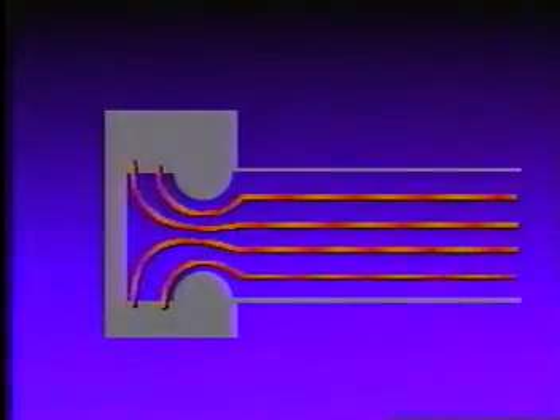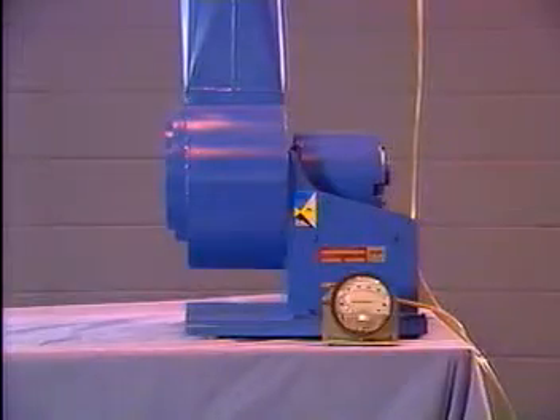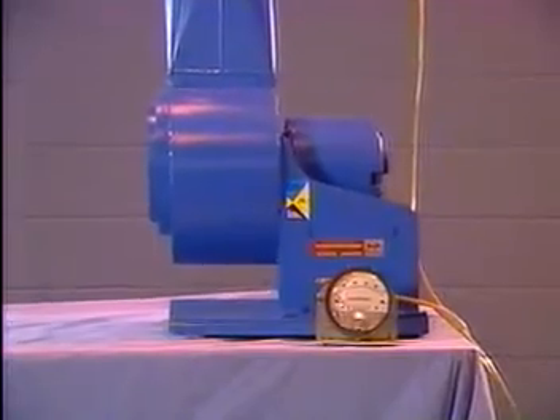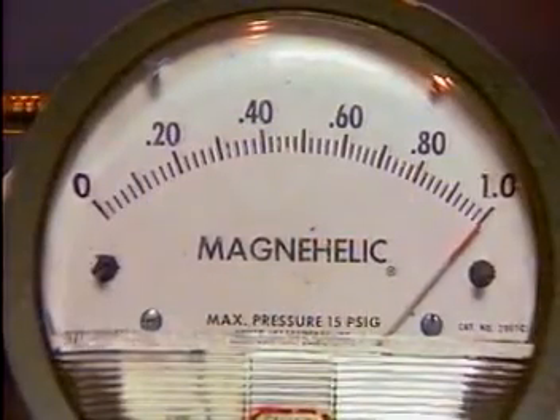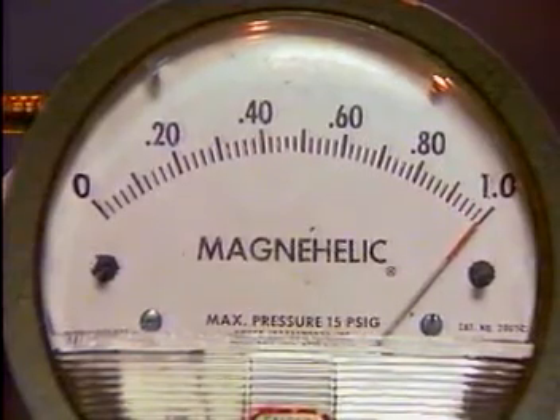To maximize inlet efficiency and fan performance, air must be drawn into the fan with an evenly distributed velocity profile. With this forward curved 8-inch fan, the Magnehelic gauge shows we're generating 1 inch of static pressure under these ideal conditions. For the purposes of this presentation, we'll use this ideal reading as a point of reference.